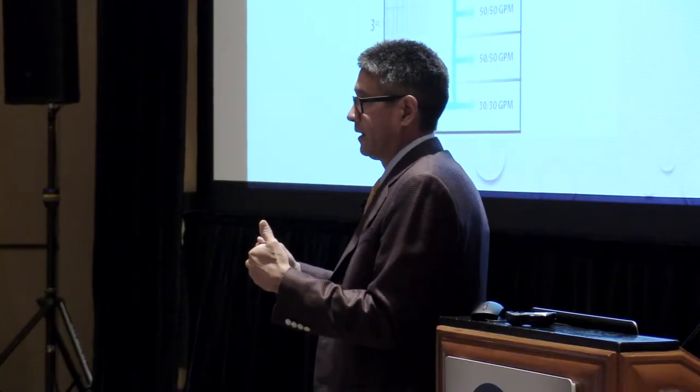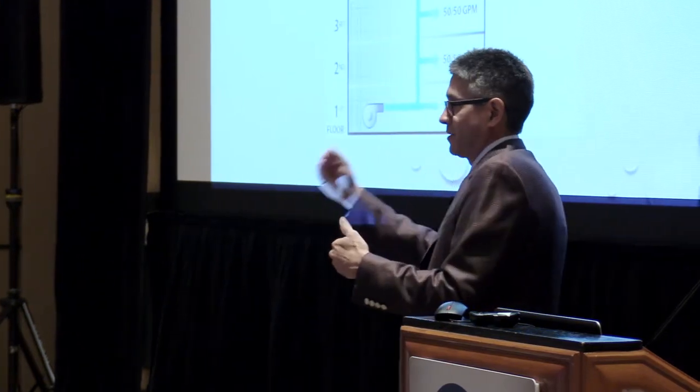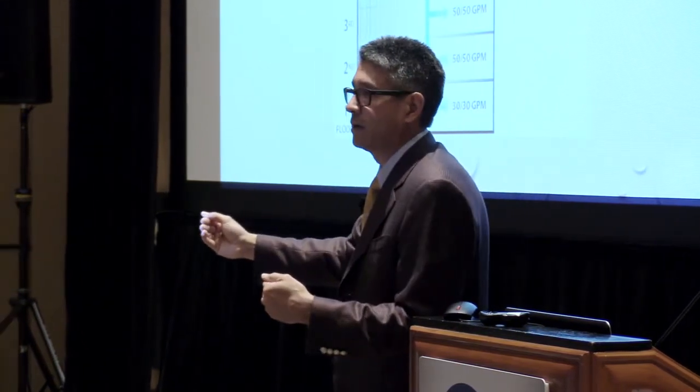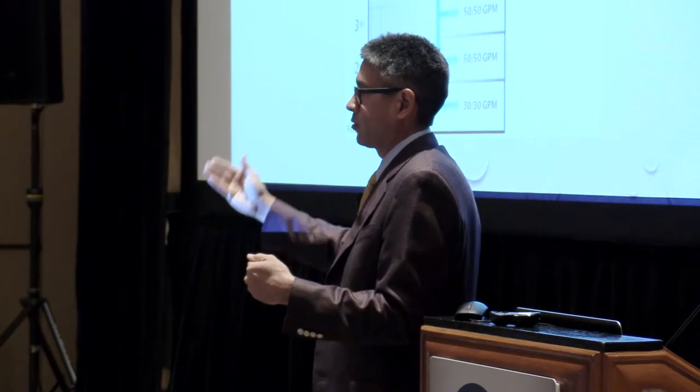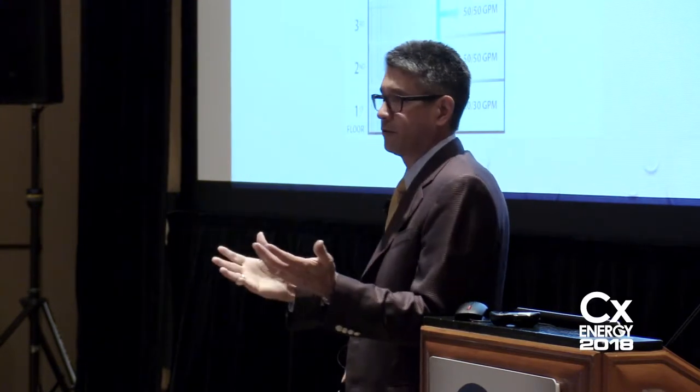Well, the next thing you know, we get up to the top eighth and ninth floor and we have no water flow. At that point, everybody starts to think, well, hold on, we can't do it that way. And it's always funny, the next comment that typically comes is, balance it to diversity. That'll work even better. So balance it to diversity.